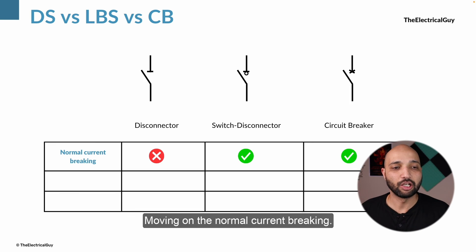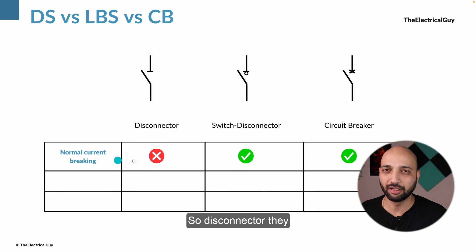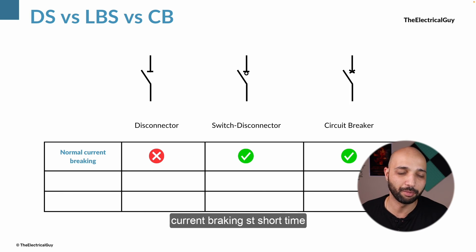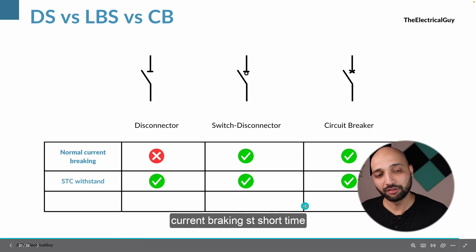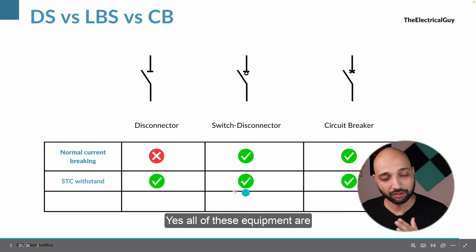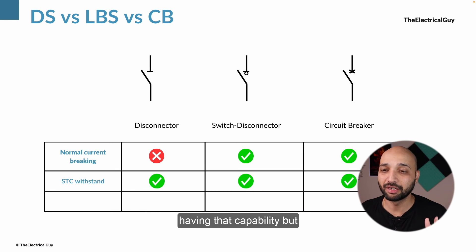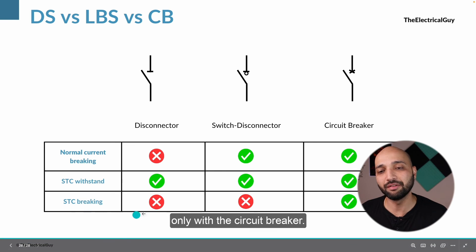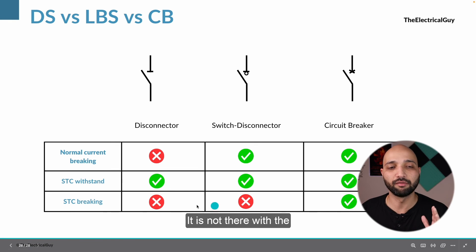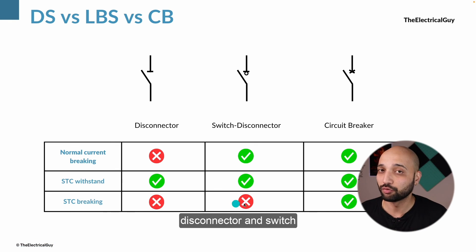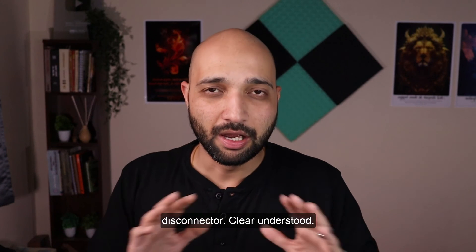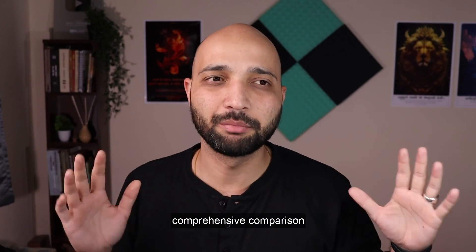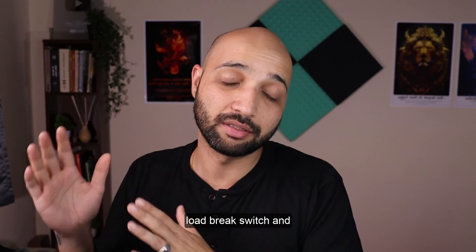On normal current breaking: disconnectors are not capable, while switch disconnectors and circuit breakers both can perform normal current breaking. For short-time current withstand capability, all three devices have this capability. However, the breaking capacity for short circuit currents is only available with the circuit breaker — it is not present in the disconnector or switch disconnector. That completes the comprehensive comparison between disconnector, load break switch and circuit breaker.